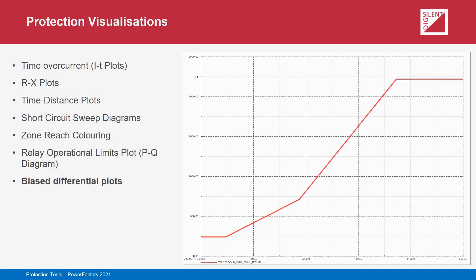The behavior of differential relays can be monitored using biased differential plots. Differential characteristics showing the restraint and operate regions of the relay on a stabilizing current versus differential current plane can be plotted. Additionally, phase comparison plots on a complex plane can be plotted for relays employing this particular technique.